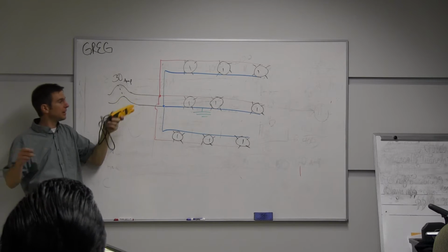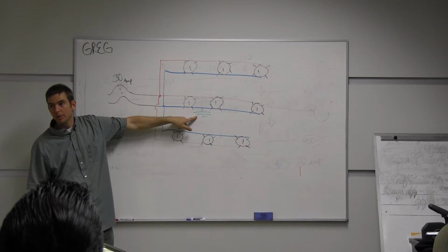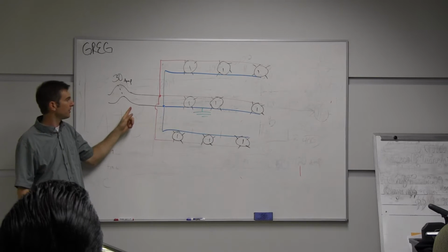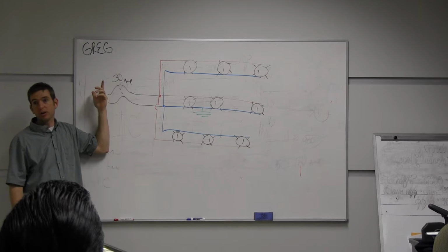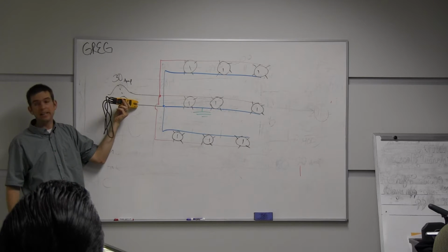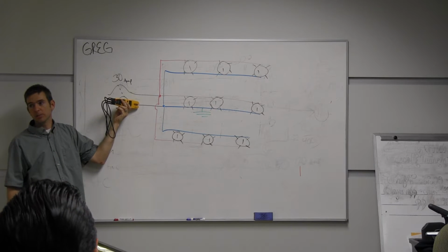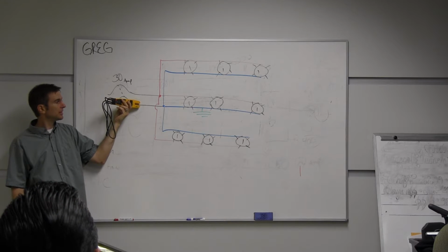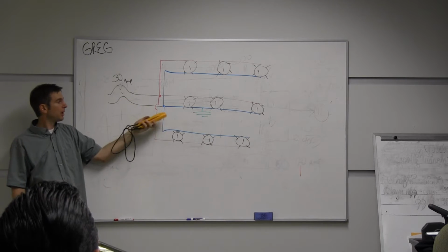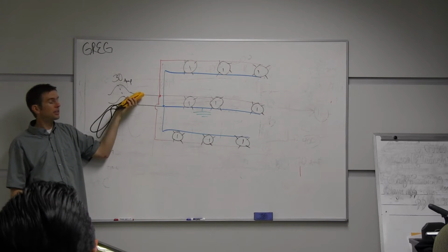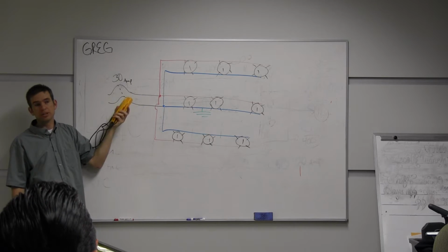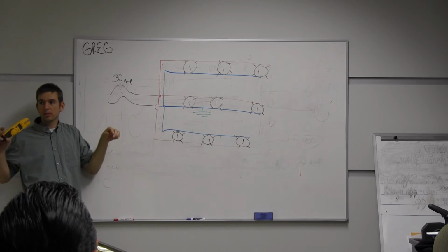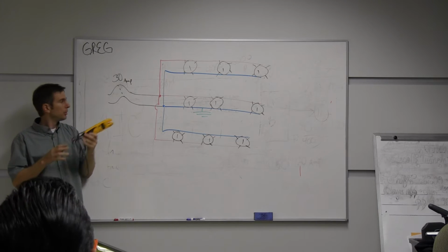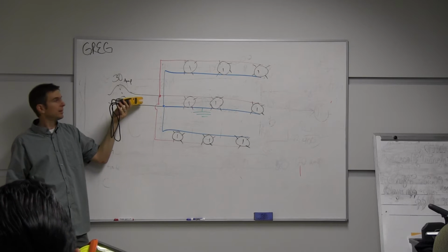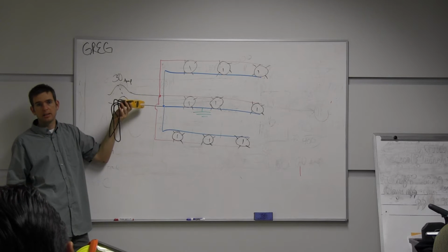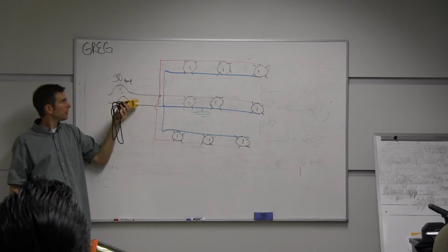I'm not going to see 9 this time, because remember, we're grounded. It's going to be in excess of 9. It's tripping the 30 amp breaker. I don't know how much it's going to be, but it's going to be over 30 amps. So if I'm checking this one, it takes 5 seconds for the breaker to trip. I see 30 amps on this. I know I have a problem on this wire, and I know that this wire is fine. So we've just determined that without becoming exposed to live conductors, we're using an amp probe. I know that this wire is bad, this wire is good. This one has 9, this has more than 30.